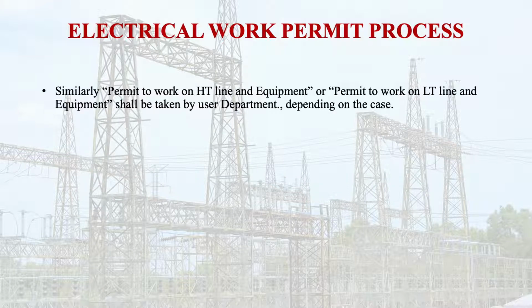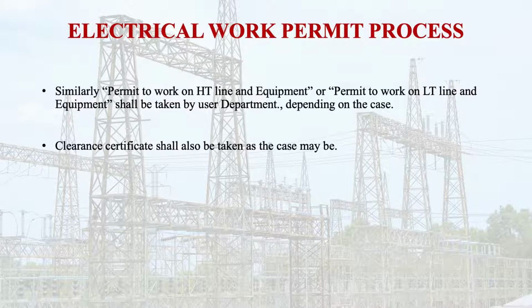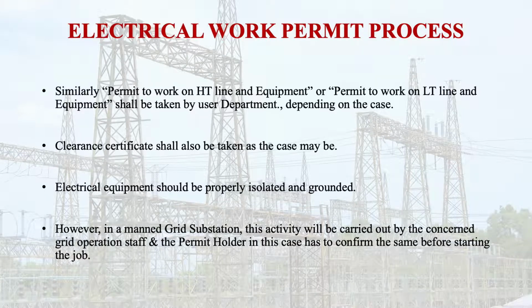Similarly, permit to work on high tension line and equipment, or permit to work on low tension line and equipment, shall be taken by the user department depending on the case. So clearance certificate shall also be taken as the case may be. Electrical equipment should be properly isolated and grounded. However, in a manned grid substation, this activity will be carried out by the concerned grid operation staff, and the permit holder in this case has to confirm the same before starting the job.